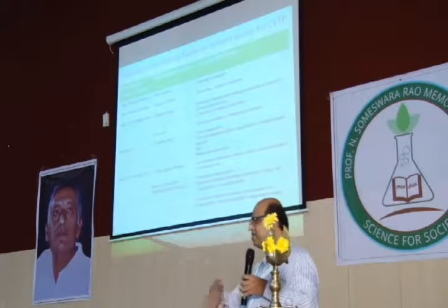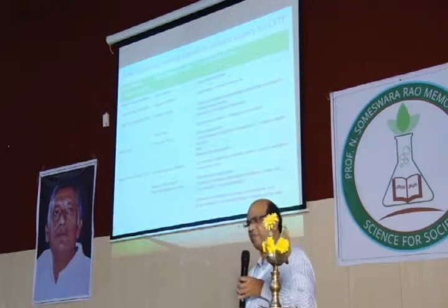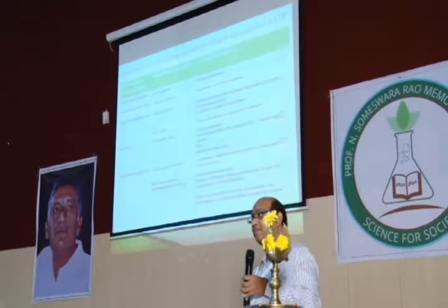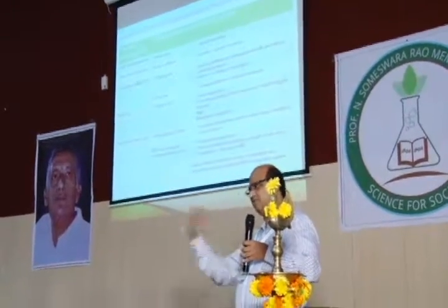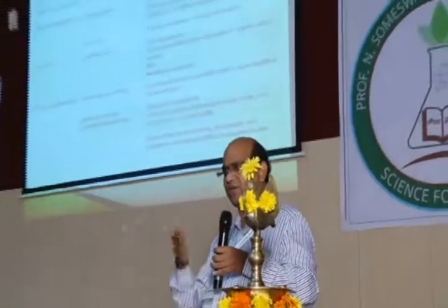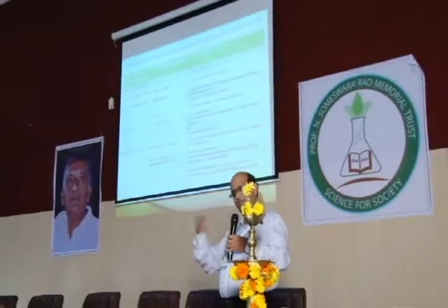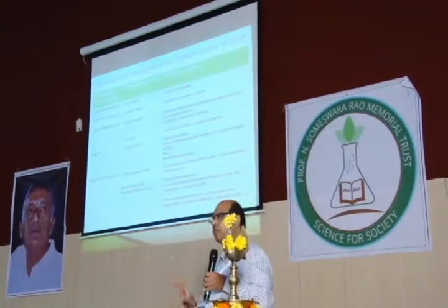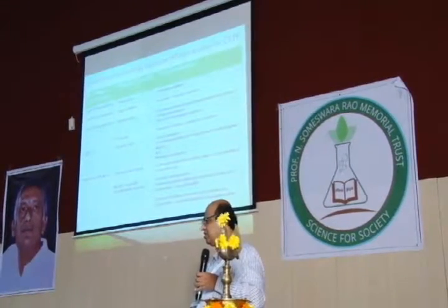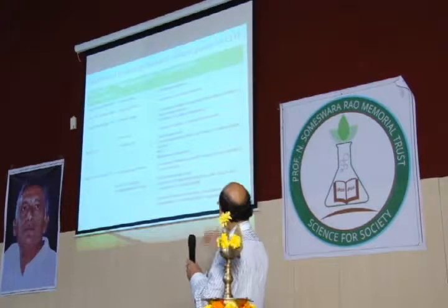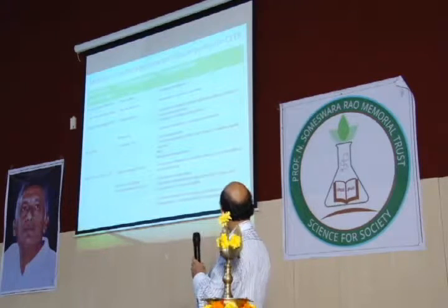Because MEE means what? MEE followed by ATFD also. That becomes very, very important. MEE is okay, but sometimes water with all organic matter will be there. MEE concentrates are highly organic. Automatically an agitated thin film dryer must follow the MEE, the multiple effect evaporator, of course with different stages, sometimes 3, 4, 5 also. Then of course ATFD, the agitated thin film dryer, is working wonderfully, so we are getting mostly wonderful results immediately. Then, of course, here incineration and thermal decomposition, and of course, there are different techniques.